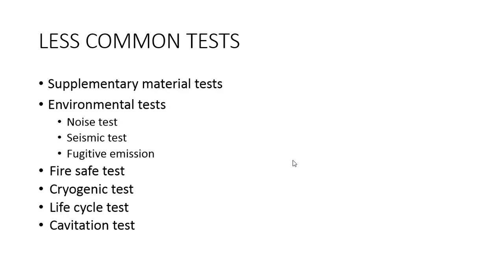What are the few less common tests in the control valve? Supplementary material test. It is given by ASTM standard and is requested by the customer. In ASTM A216, impact test, hardness test, and microstructure test are considered. Also corrosion tests are there as per NACE specification and as per customer requirement.